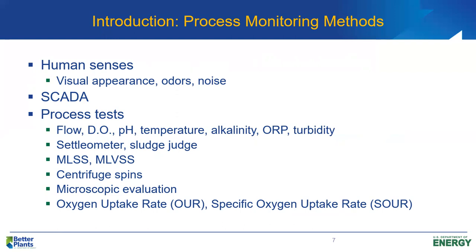The process tests we use include flow rates, dissolved oxygen levels, pH, temperature, alkalinity, ORP, settleometer, sludge judges, mixed liquor suspended solids concentrations, microbial evaluation using a microscope, and OUR and SOUR. All of these are important tests that we use conjunctively to tell us what's going on in the activated sludge process. Each test is valuable and gives us information about the overall status of our process. We rely significantly on these data.